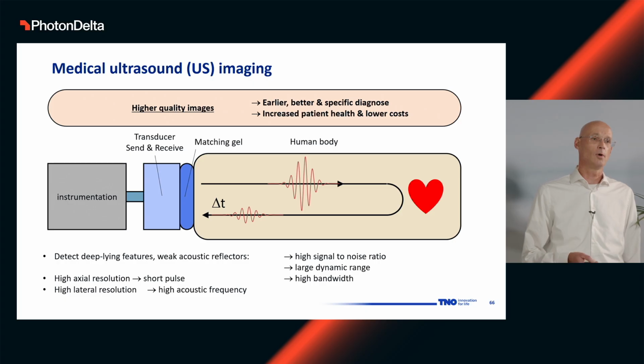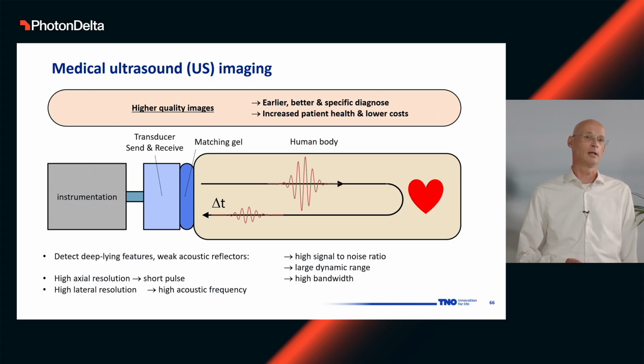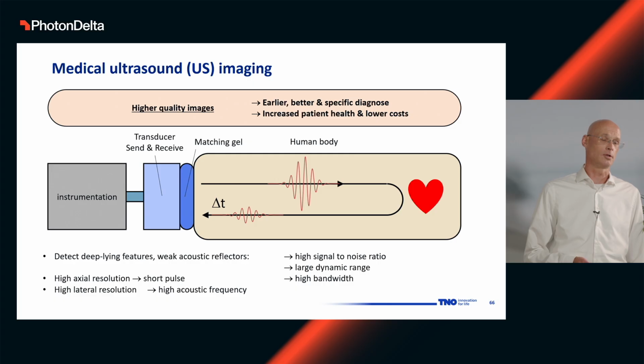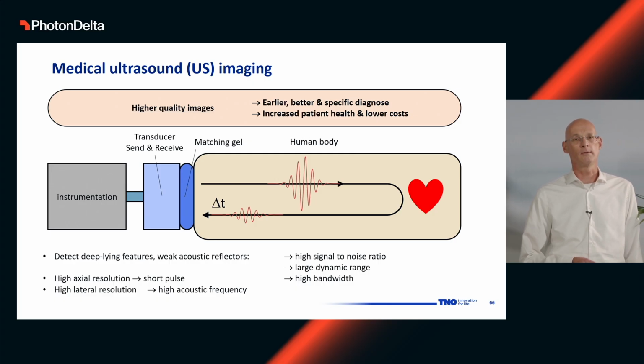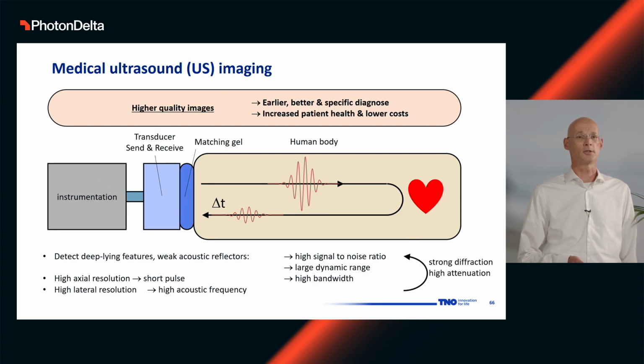Then, to have a high axial resolution, you need to have this pulse to be very short. And the short pulse means that you have a high bandwidth of your acoustic signal. And also for high lateral resolution, you like your acoustic wavelength to be small, meaning high frequency. So these are some key parameters, and they're also intertwined. Because if you go to high acoustic frequencies, that means you have stronger diffraction, and it means you have stronger attenuation by the human tissue. And that immediately feeds back to high signal-to-noise ratio and large dynamic range.